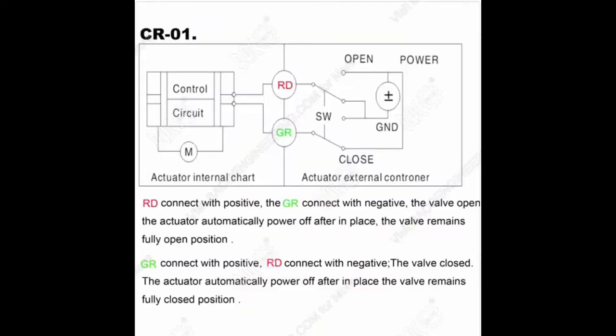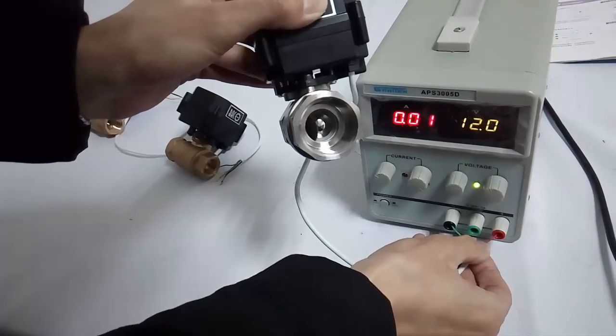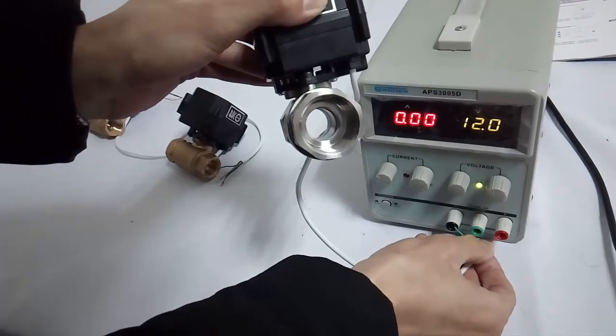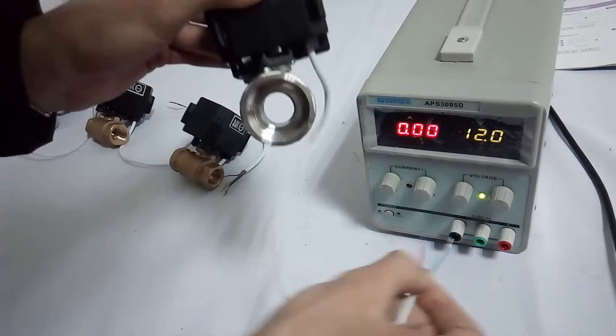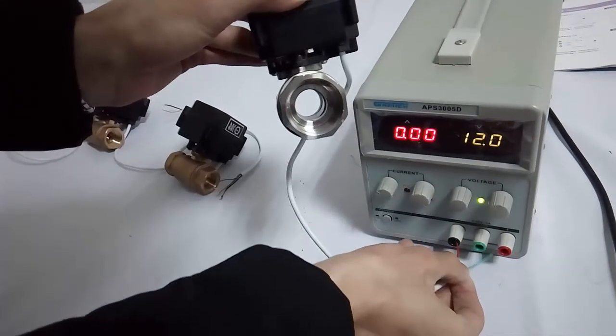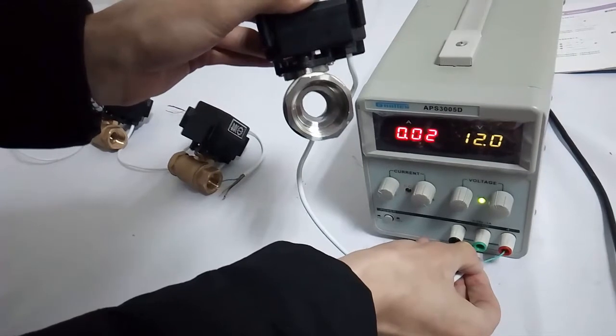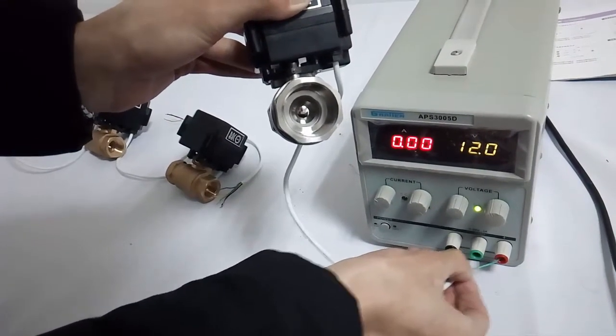Wiring diagram CR-01: It has a red wire and a green wire. When the red wire is connected to the positive pole and the green is connected to the negative pole, the valve will be opened. Power off automatically after in place. On the contrary, when red is connected to the negative pole and green is connected to the positive pole, the valve will be closed. Power off automatically after in place.